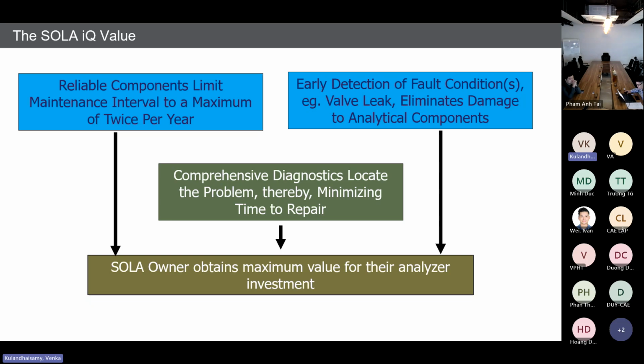SOLA 2 needs at least 2 to 3 hours, because the problem is SOLA 2 has a silica U-looped tube that is very fragile. Whenever you want to install that glass tube, you have to be very careful and very patient. That's why it will take almost 3 hours to dismantle and then assemble the pyrolyzer assembly. But SOLA IQ, within 30 minutes we can replace it. It has a ceramic tube which is not fragile. It is very strong. You easily remove the quarter-inch ferrule at both ends, then you can remove the ceramic tube easily.